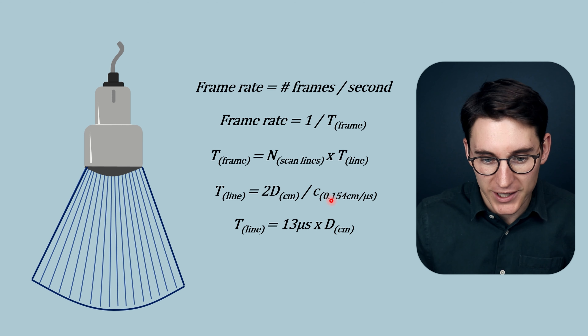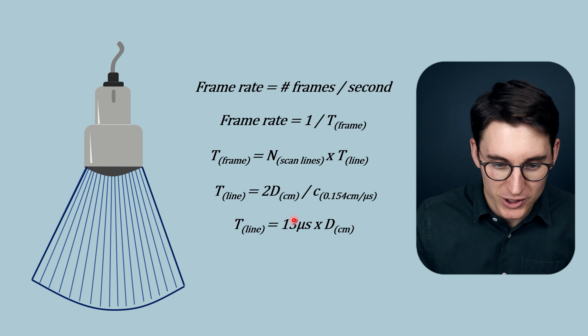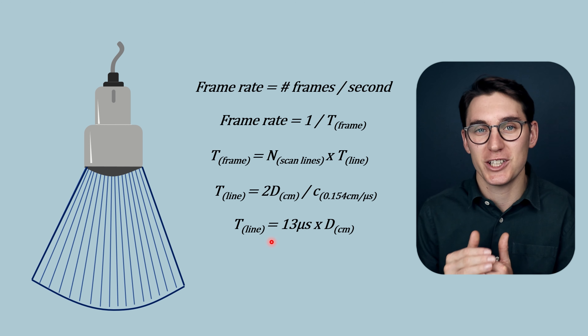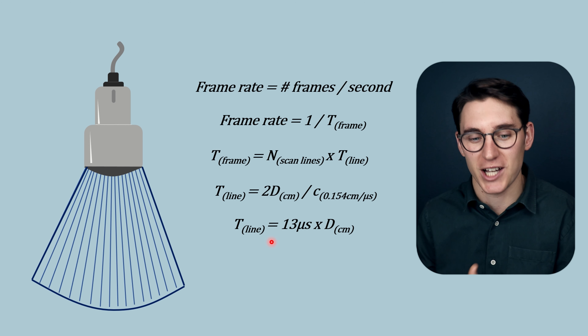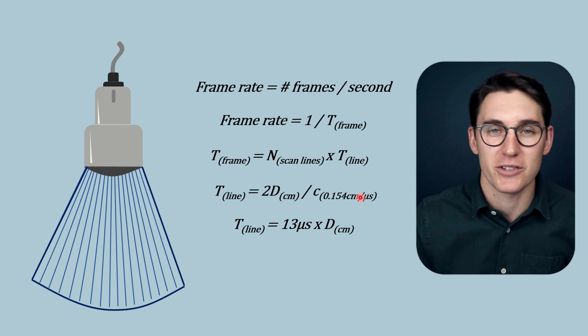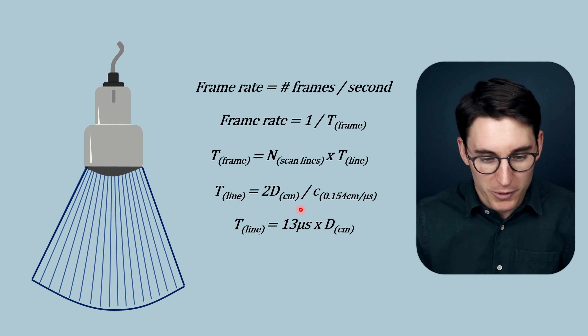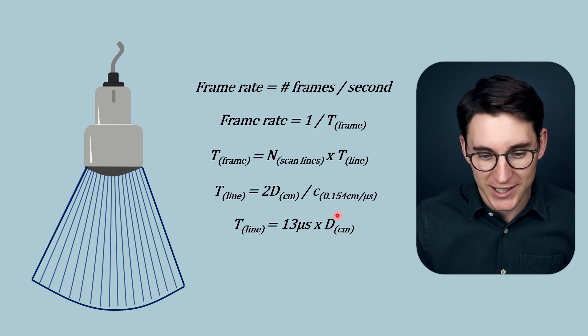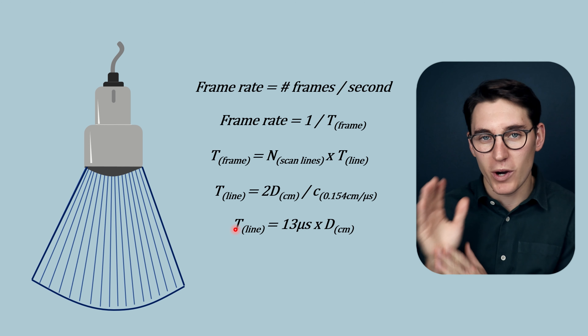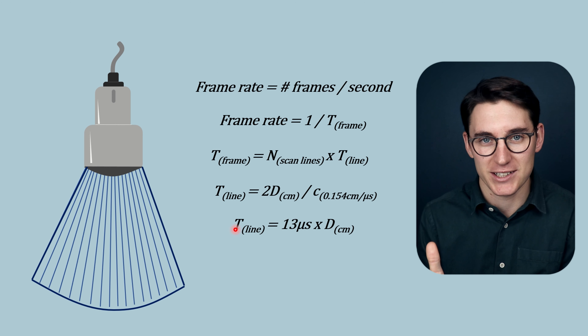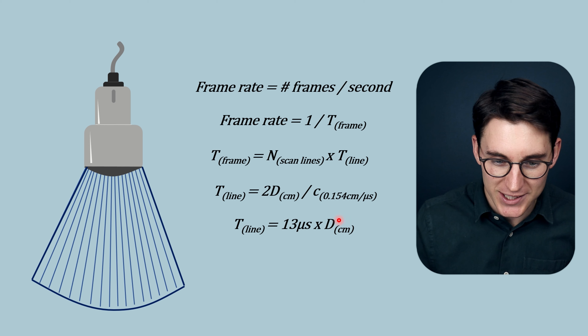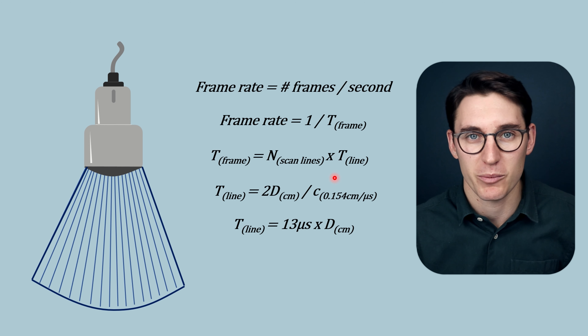Two divided by 0.154 gives us 13 microseconds. This formula is specific to soft tissue — if imaging another tissue type, this formula would not apply. From this equation, we can see that increasing our depth increases the time it takes to acquire a single A-line of data for the entire field of view, and that changing the depth will ultimately affect our frame rate.